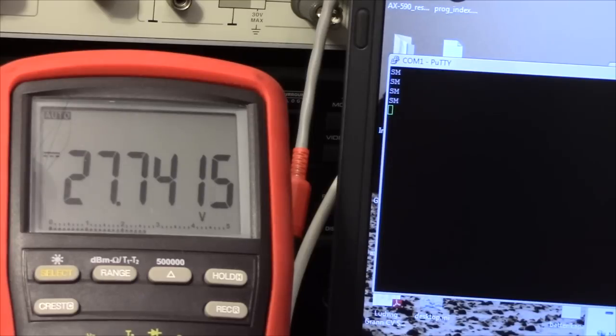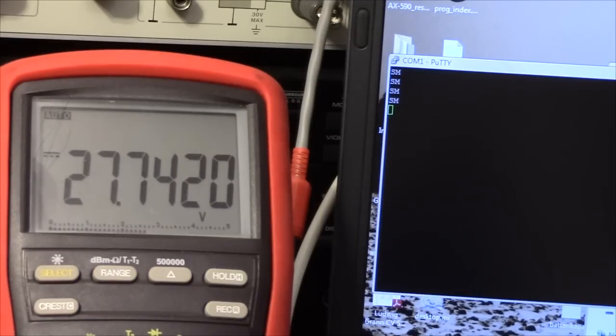The way you adjust this is by putting the UPS, well, first you need to hook it up with a serial cable, which I've done to my laptop here, and you can connect to it by just starting a serial connection or something equivalent. If you press Y it'll tell you it's a smart unit by telling you SM. After you've established your connection, you put the unit into configuration mode by pressing 1, waiting a couple of seconds and then pressing 1 again, and you get a PROG out of the unit.